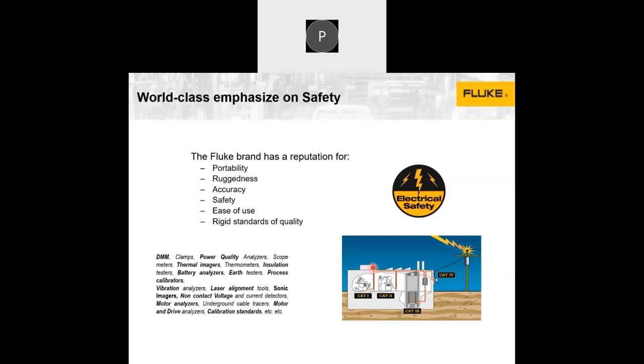That means there is a reason for safety risk in your electrical systems, where you have 110 or 230 volt present, the highest voltage transient expectation is up to 4,000 volt, or 4 kV. Where three phase lines or LT lines are present, the expected voltages are up to 6,000 volt or 6 kV, and above that, in exposed lines and open fields, it can be up to 8 kV and above, sometimes even 12 kV.